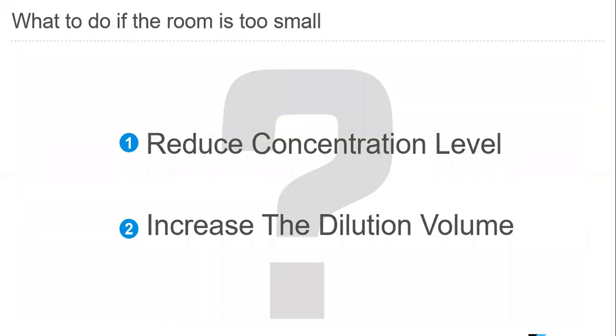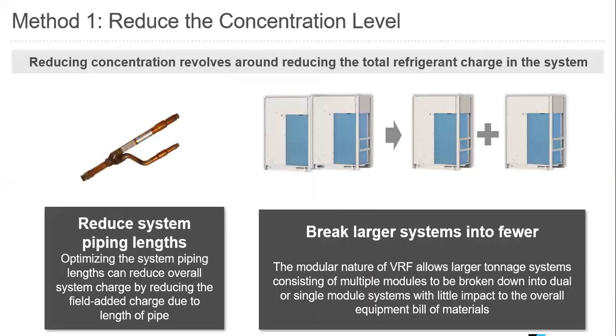So that's step 4. So what do we do if a room is too small? Well, we have 2 different options. We can reduce the concentration level, or we can increase the dilution volume. So reducing the concentration level revolves around reducing the total refrigerant charge within a system.